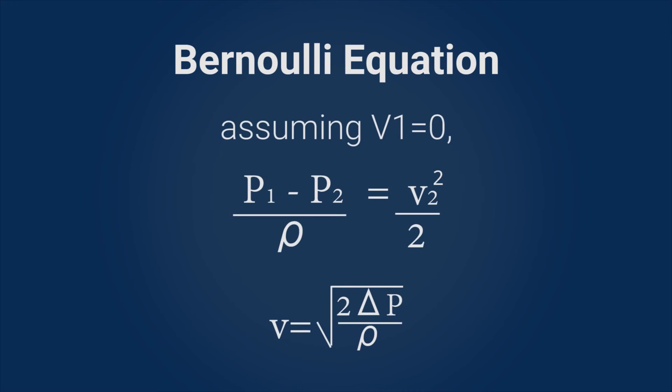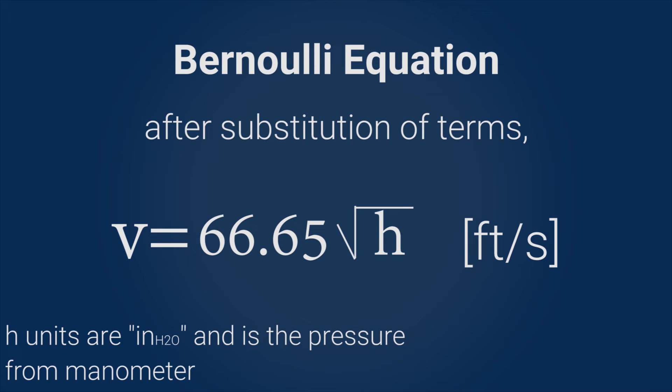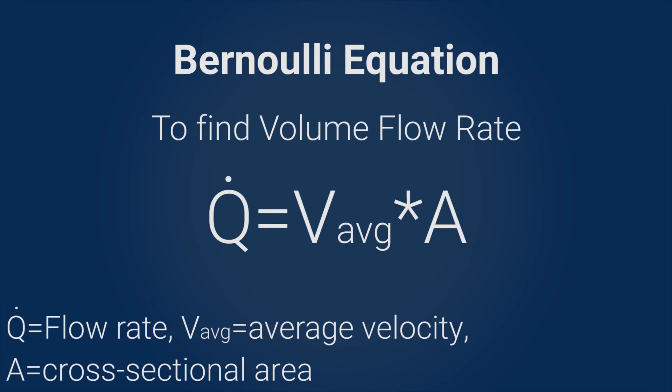After some arranging and substitution of terms, we arrive at the following equation: velocity is equal to 66.65 times the square root of the pressure reading in inches of water, which gives us units of feet per second. Once we have the velocity, the volumetric flow rate can be calculated by multiplying the average velocity times the cross-sectional area of the duct.